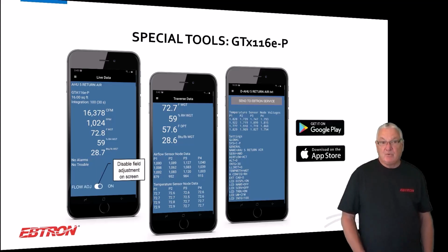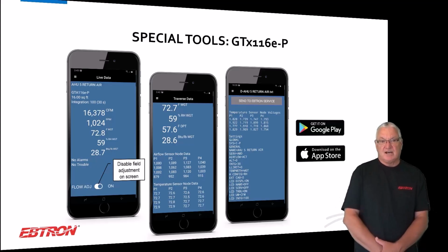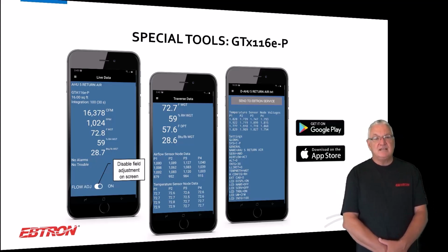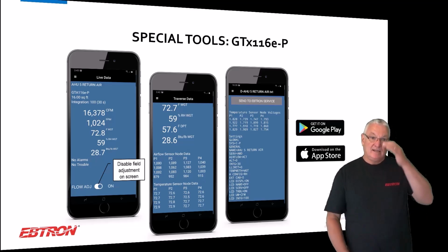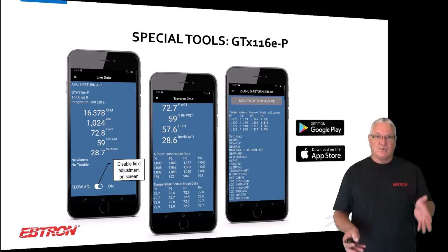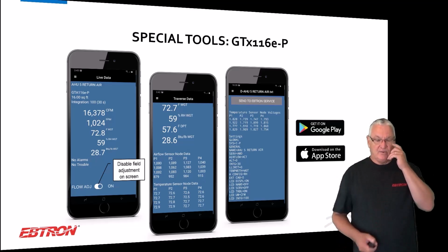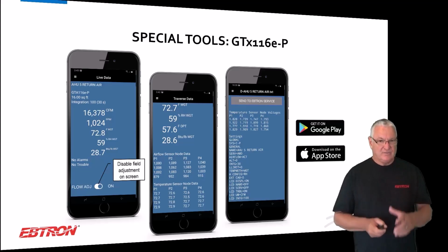If somebody went in and adjusted the EBTRON, this button will show up. It says flow adjust on. You can turn it off to see what the EBTRON read out of the factory. It does not affect anything in terms of what it's reading at the device, okay? What the output of the device is. It's just you on the phone.